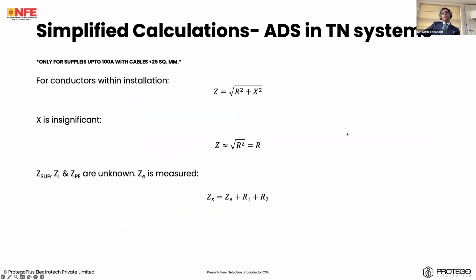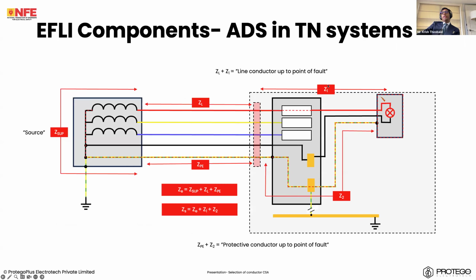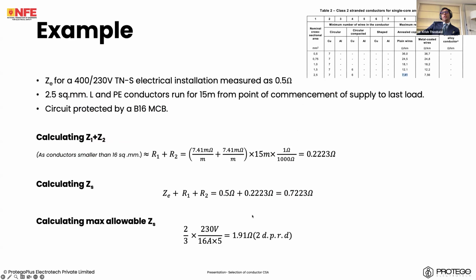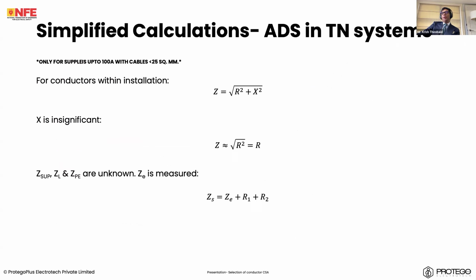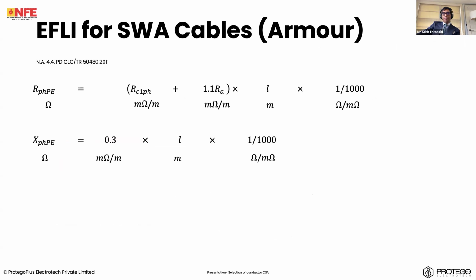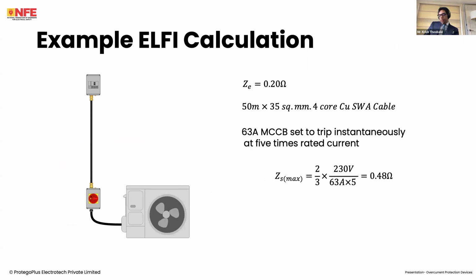Now, like I said, for cables up to 16 square mm or lesser than 25 square mm, instead of Z1, Z2, we can consider R1, R2, the resistive component. This is what I've done here. However, this cannot be done if we have bigger cables or if we have armored cables. Now, this is going to be a very interesting slide. I'll show you a picture here and I want you to go on a little bit of a story with me.